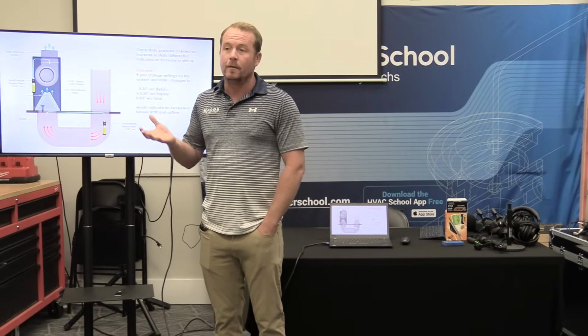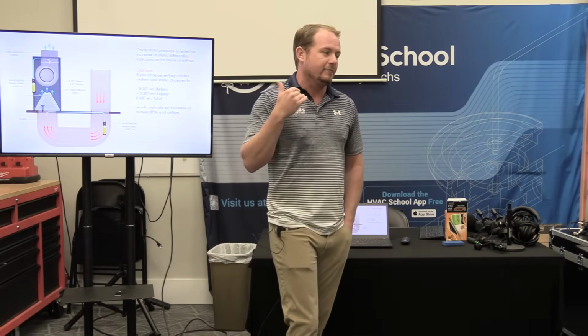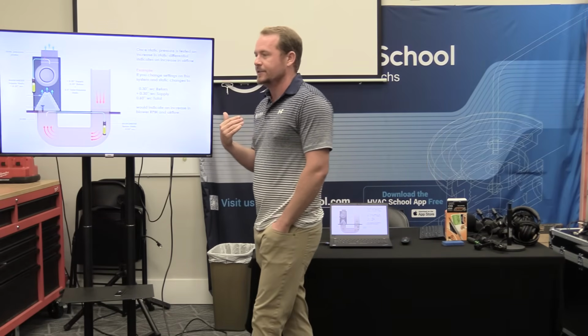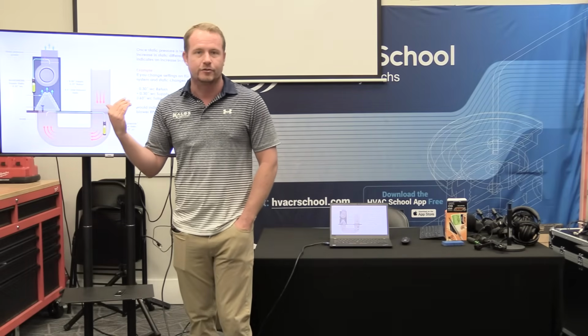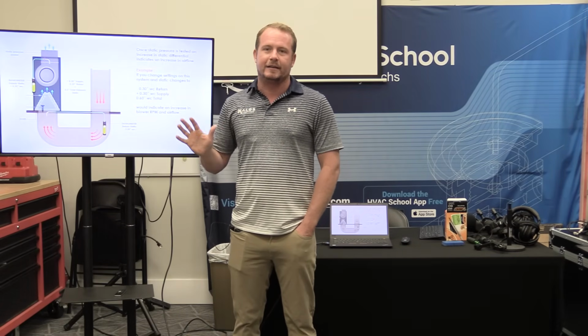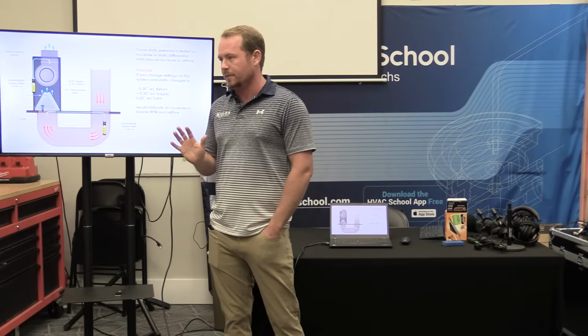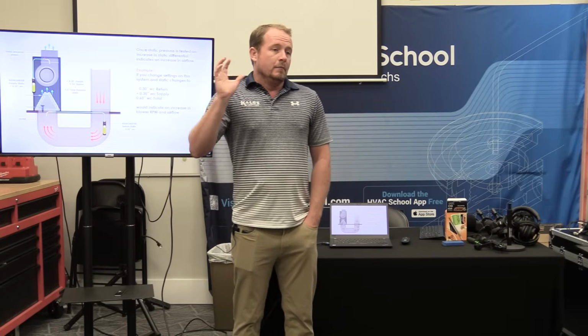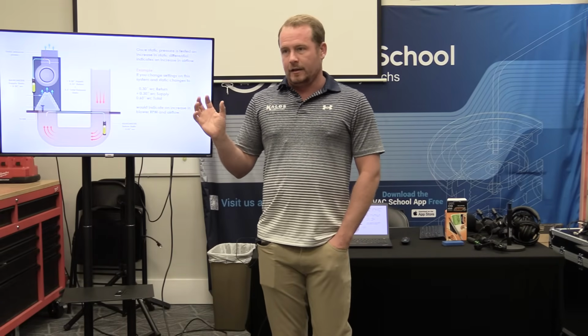Make sense? So for those of us who aren't in the habit of measuring static pressure regularly, I know a lot of us aren't. And again, I'm not one of these guys who says every time you change a capacitor or clean a drain, you need to check static pressure. It isn't a stock practice that we do every single time we touch a piece of equipment. I find that to be overkill. But when you do certain things, it is valuable.